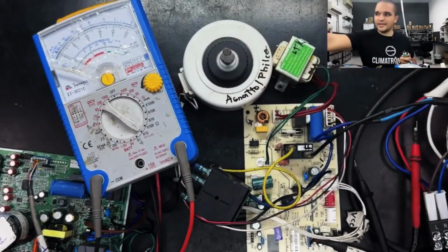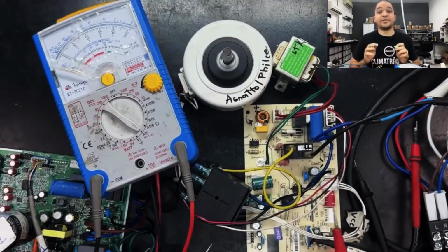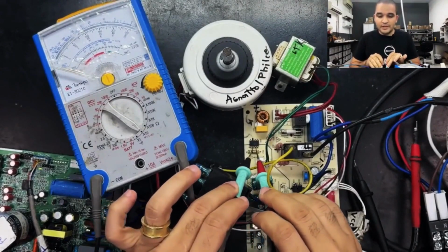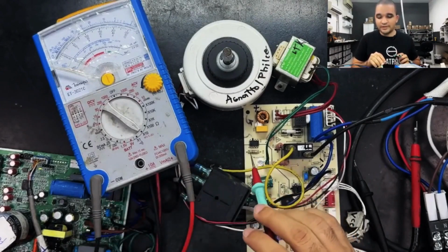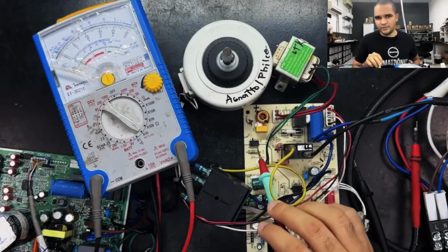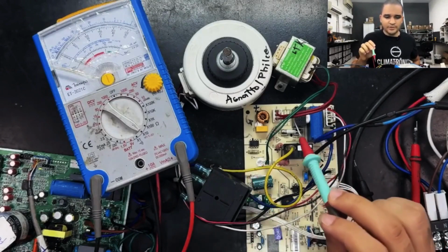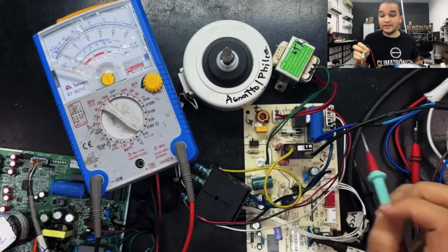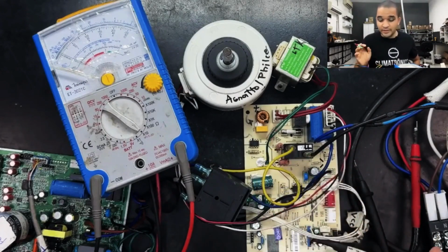I understand that the fan isn't starting, and I want to determine if it's the fan itself or the activation circuit. To discern what is activating in this component when I activate it here, I'll obviously analyze its datasheet or the circuit traces to comprehend its function. It's an optotriac, this small black component here, which will send a signal to the fan to initiate. If I activate it and the motor turns, then the motor is functioning properly. The power circuit is operational, which we refer to as the hot circuit. However, the cold section, which is the low voltage section, is malfunctioning.